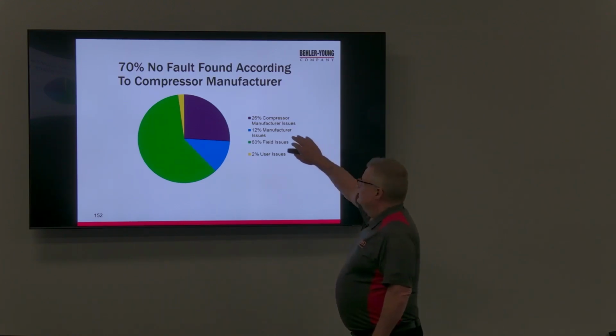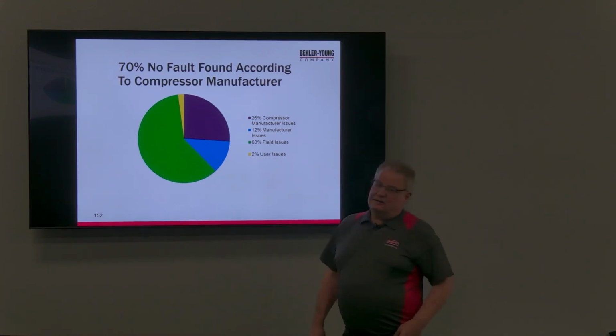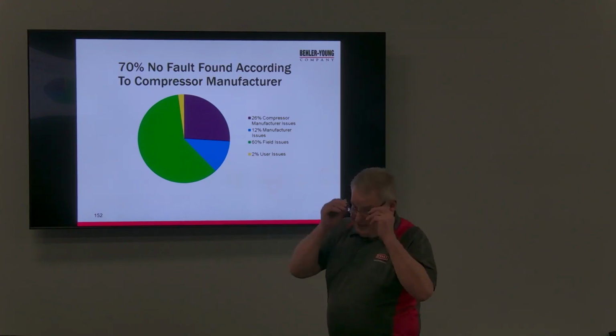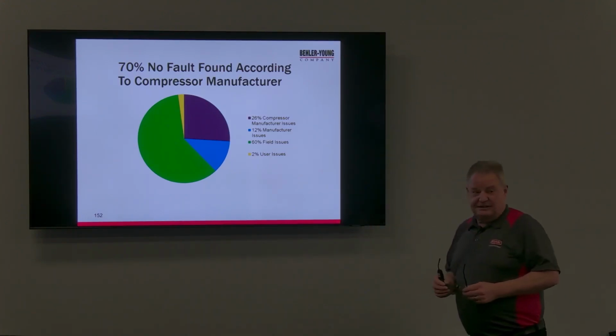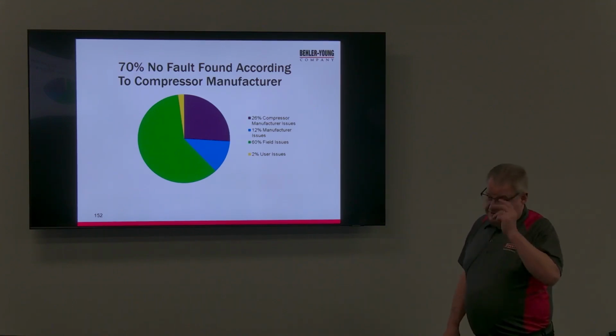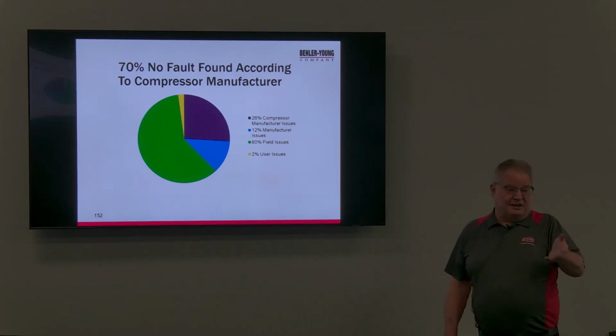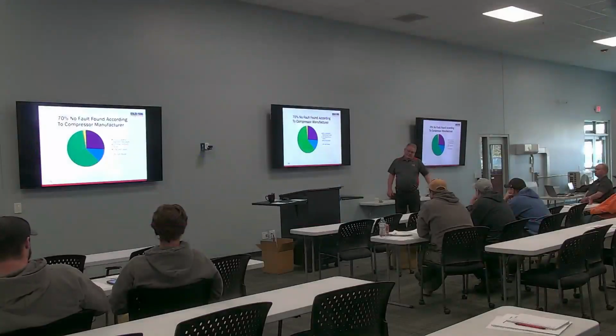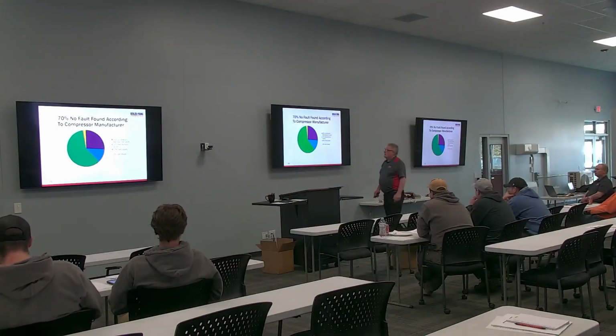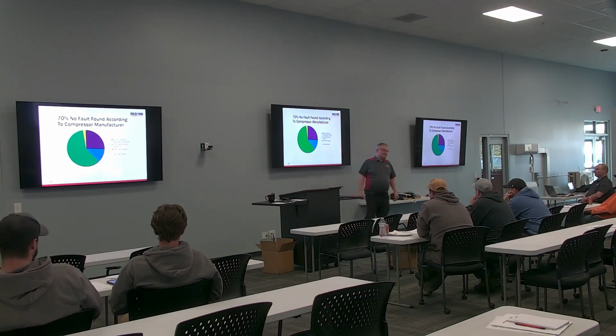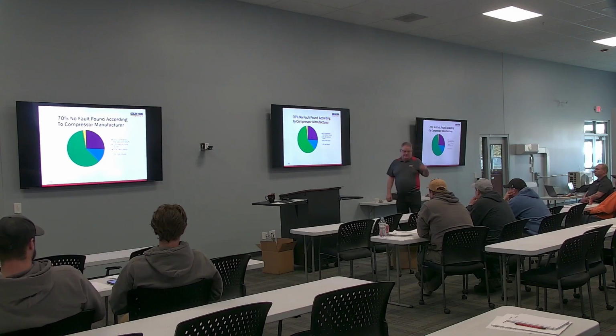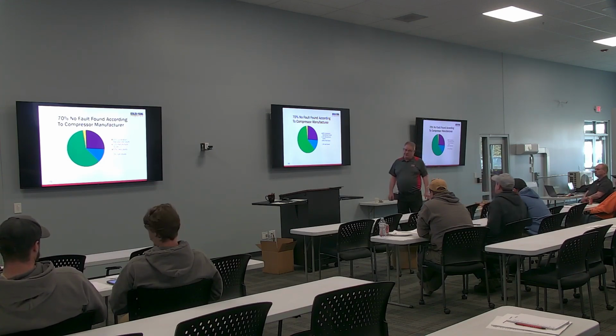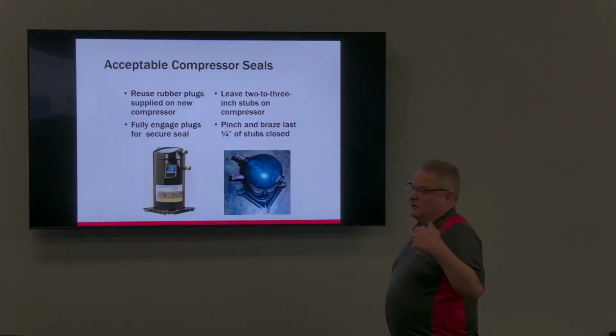Copeland claims that no compressor failure is their fault. Well, I'll disagree with that, because the K7 series that we went through about 2 years ago was their fault. And that rust inhibitor that caused the TXV problem, that was their fault, but it's not ever their fault. So anyways, when you look at their report, more than 60% of compressor failures are field issues. We got moisture in there. Moisture destroys the oil. If we destroy the oil, we have no lubrication. And once POE oil is wet, you cannot dry it out. There's just no way to do it in the field.